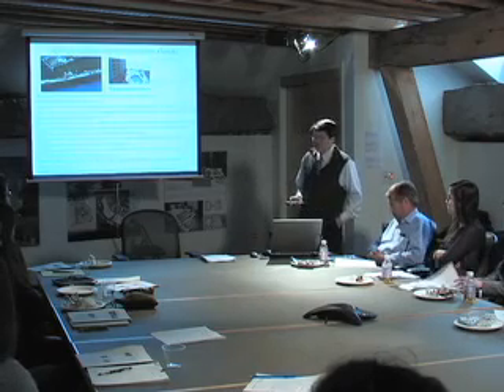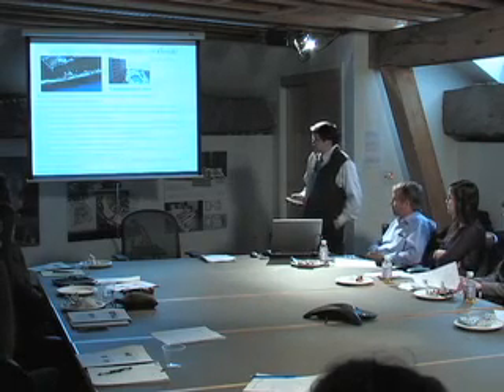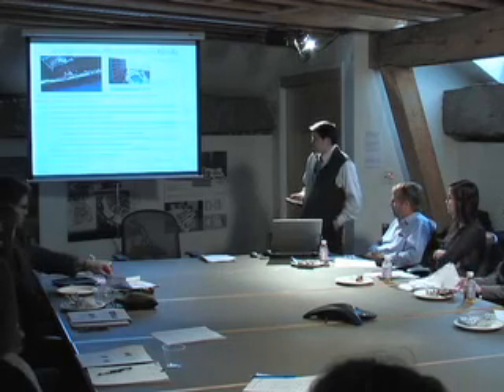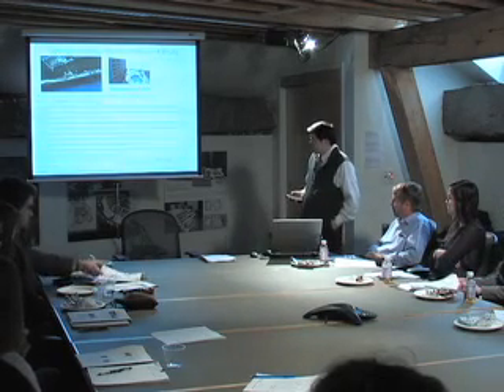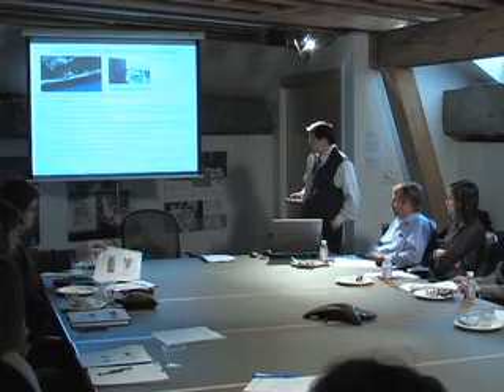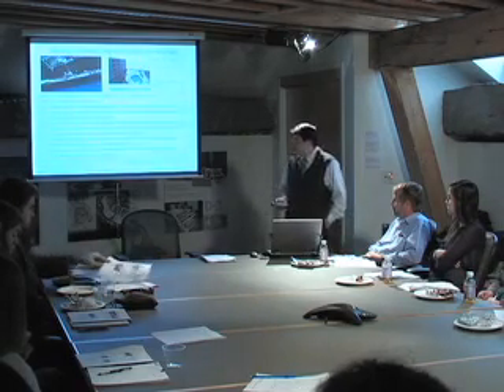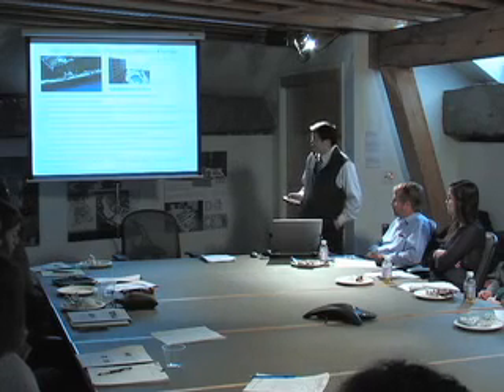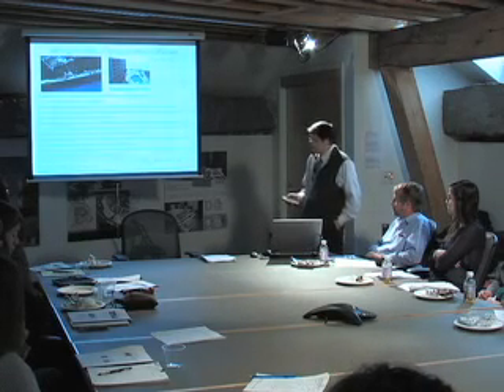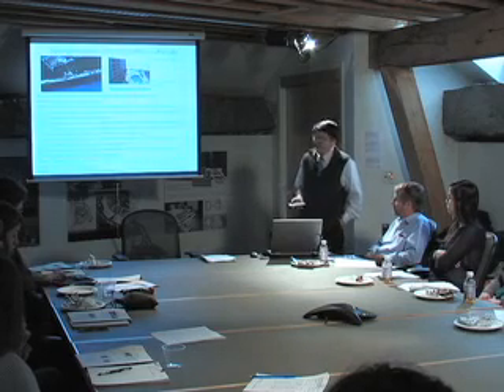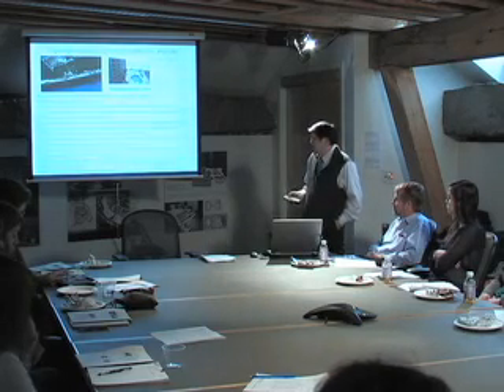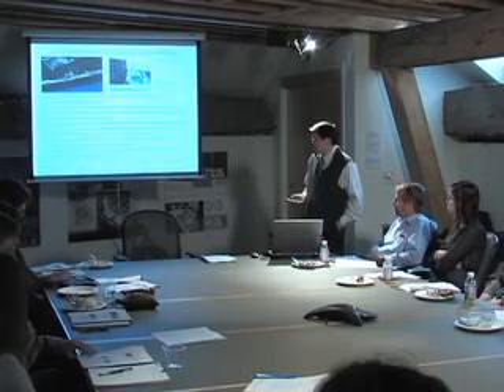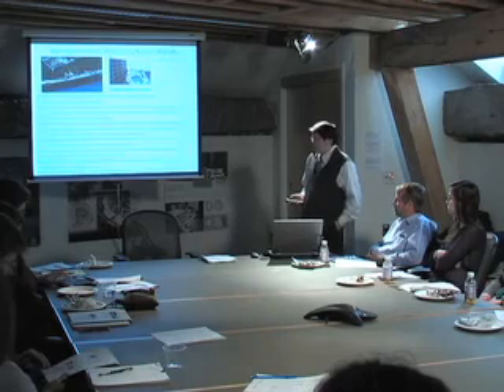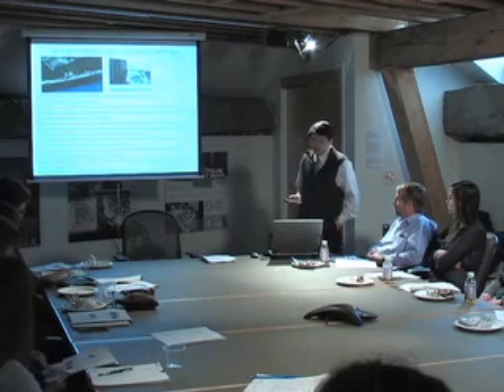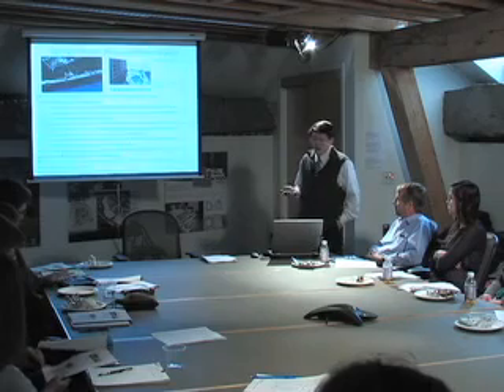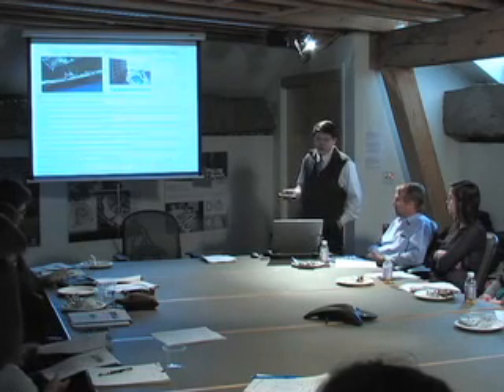The hotel opened in 2002. They metered the energy consumption for a year, and they were able to maintain the indoor air temperature at a very comfortable level. They have reported a very low maintenance cost because now you have fewer components exposed to the salty environment. You know, the salty air tends to corrode the metal parts of the equipment. They have consistent system performance and availability, low life cycle cost. Also reduced water consumption because Florida needs a lot of cooling, so the cooling towers must be running all the time. Now you are saving some cooling towers, you save a lot of water usage.